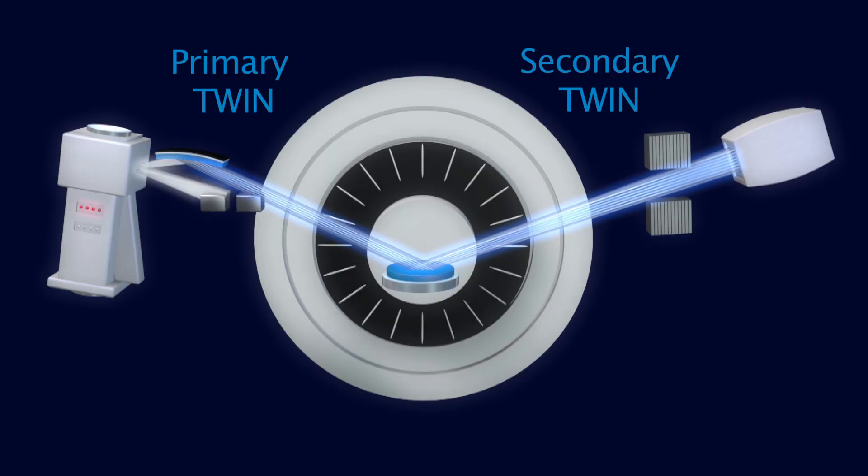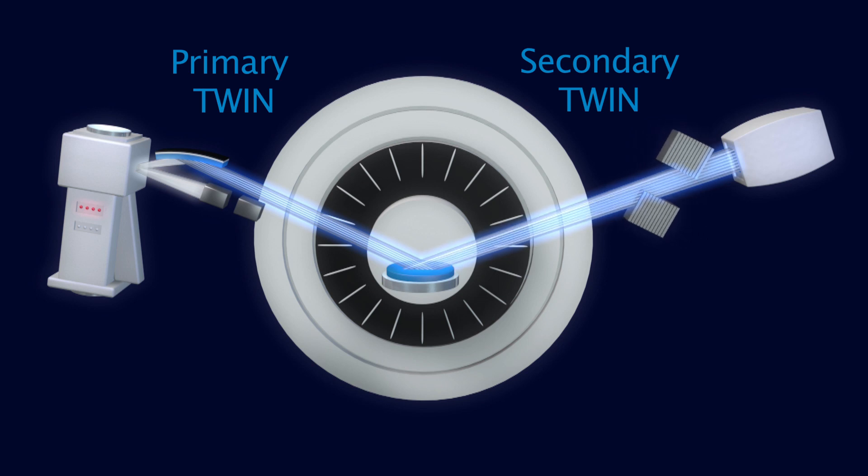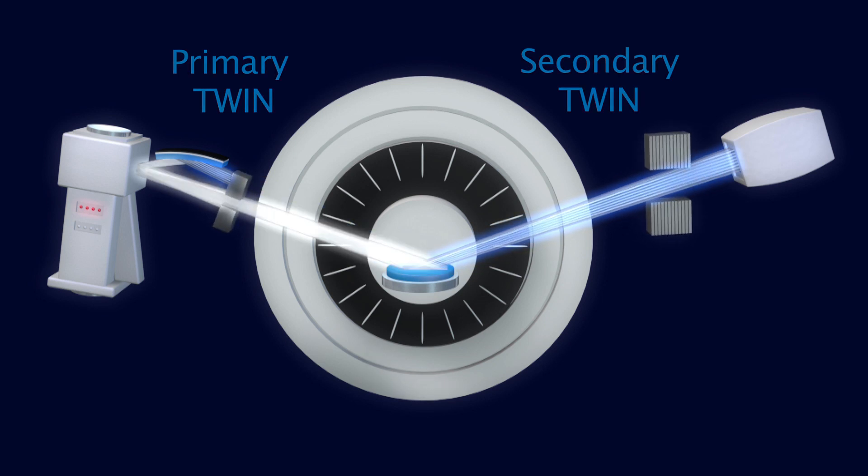The primary Twin in a Twin Twin configuration consists of a Göbel mirror and a motorized divergent slit for producing either a collimated high intensity parallel beam or a divergent beam. A secondary Twin goes on the secondary side of a diffractometer. It consists of a solar collimator for parallel beam or a motorized slit for divergent beam.